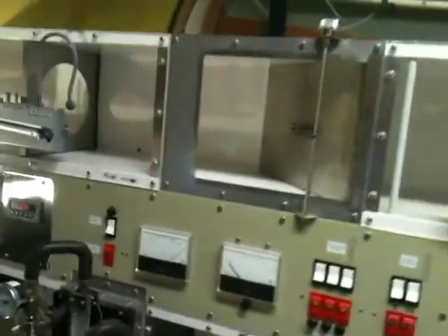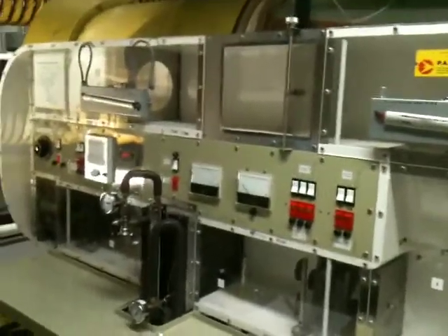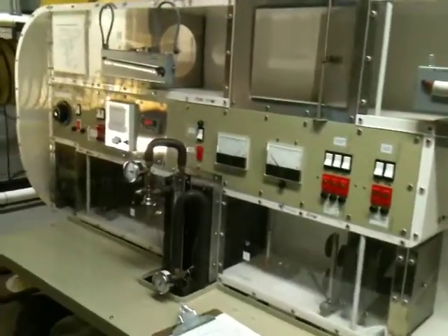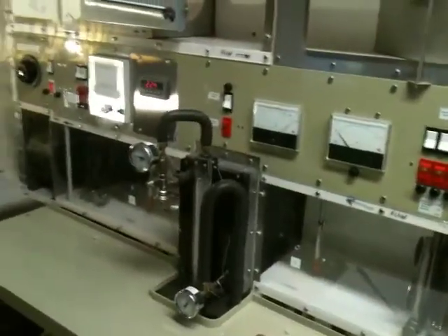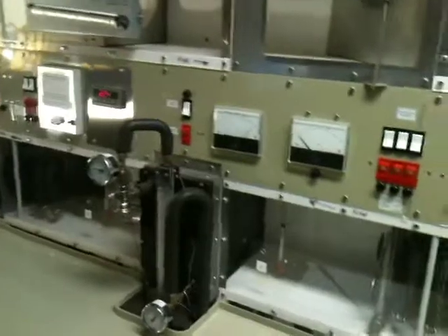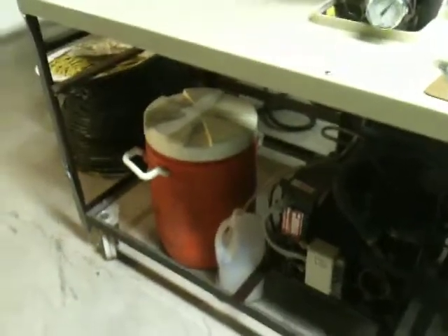And then the final test, test number 6, we are going to close the damper so we will get some flow recirculation, and we will see what effect that has on everything. We will probably get some condensation occurring at the evaporator for the cooling unit, because we're going to build up a lot more moisture in there because of the recirculation, and the condensation will come out of that tube into that jug. So we will see if we see that.